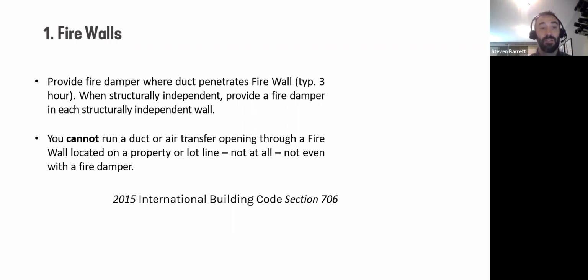But important to note that you cannot run a duct or air transfer opening through a firewall on a property line. Not at all, period. You can't do it. If 2 buildings are separated with 0 lot line with firewalls, you cannot penetrate them at all. And I've got some code sections cited here, so you can find the firewall requirements in 706 of the IBC.